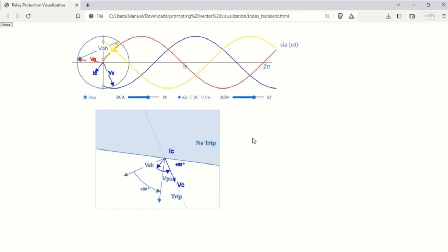By changing the X over R ratio, you can observe how the angle between phase current IC and voltage VAB changes in the visualization. This demonstrates how the system's impedance impacts the relay's ability to accurately determine the fault direction and make appropriate trip decisions.